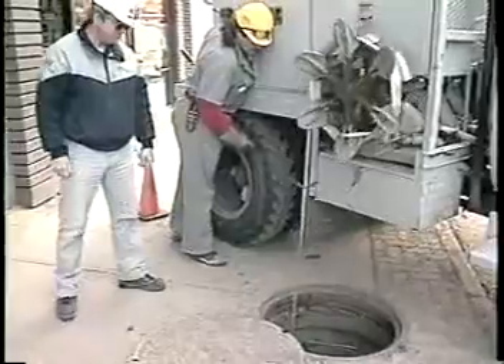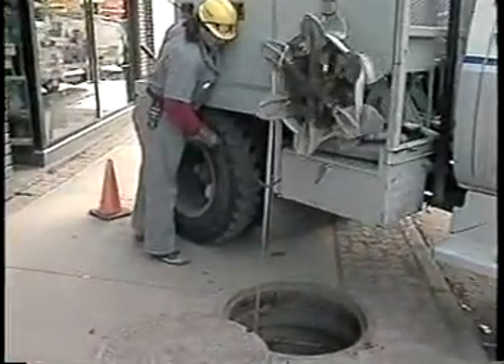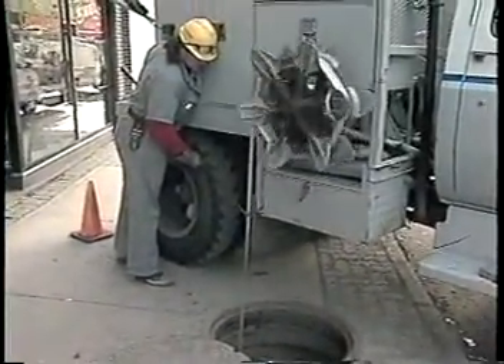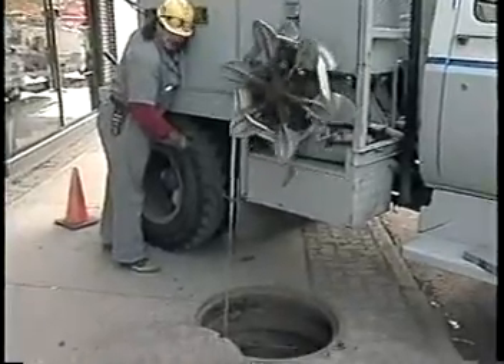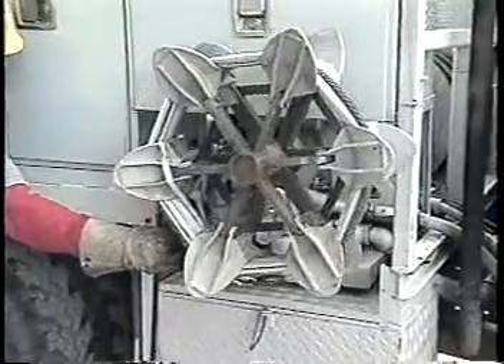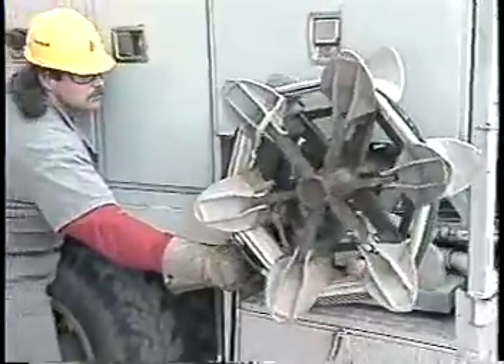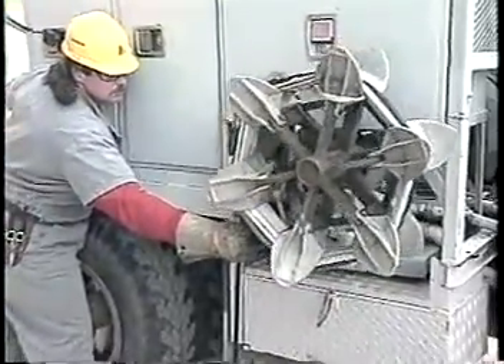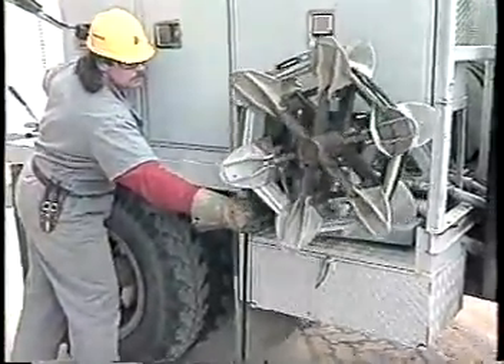When pulling cable with power-driven winches, care must be taken so that clothing does not become entangled in the machinery. Never stand in line of pulling lines, cables, or hardware under tension. If a sudden break occurs, the whiplash effect could cause serious injury or even be fatal.